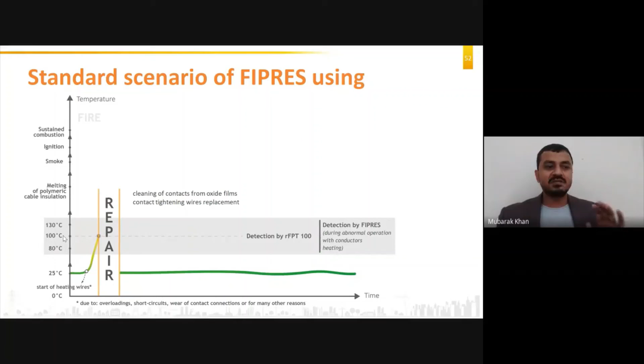Now, if you have installed a continuous monitoring system and you detected the abnormality when the temperature first reached 100 degrees Celsius, you can do the repairs and make the system normal and it will remain normal. Okay, that is why there will be no hazards of loose connection. So the first time you detect it, you go and tighten the connection, take the corrective action, and the system will become safe and normal.